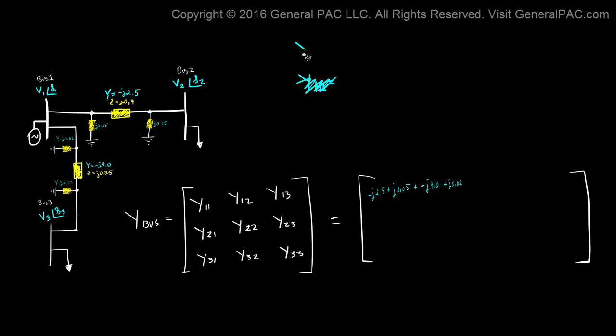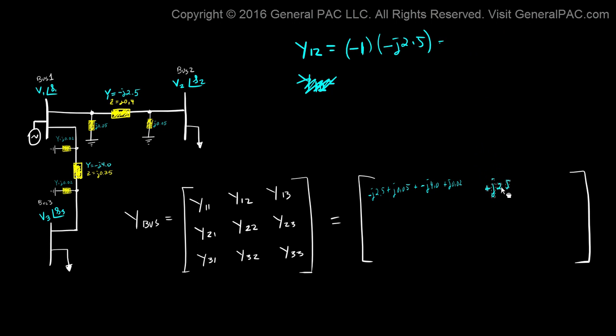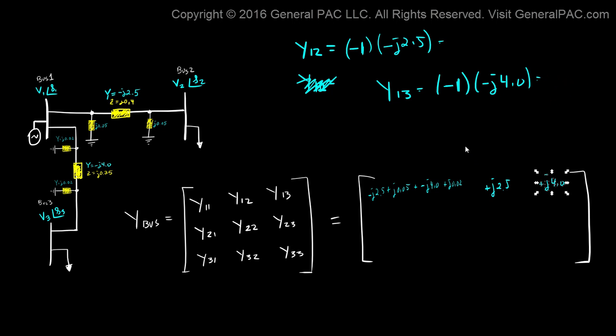Y12 is an off-diagonal element, so it equals negative 1 times the admittance from bus 1 to bus 2, which is negative J2.5, giving positive J2.5. Y13 likewise equals negative 1 times the admittance from bus 1 to bus 3, which is negative J4.0, giving positive J4.0.